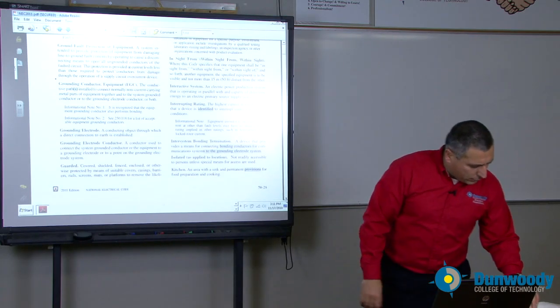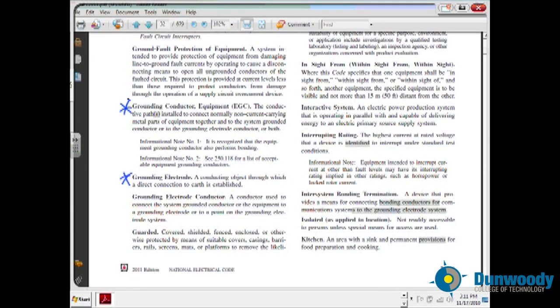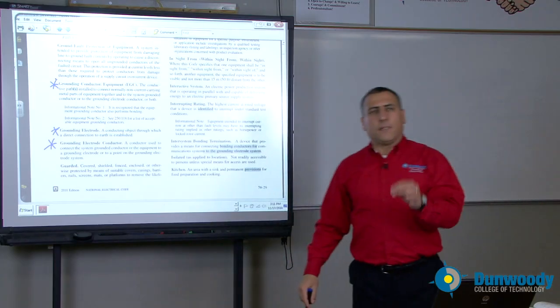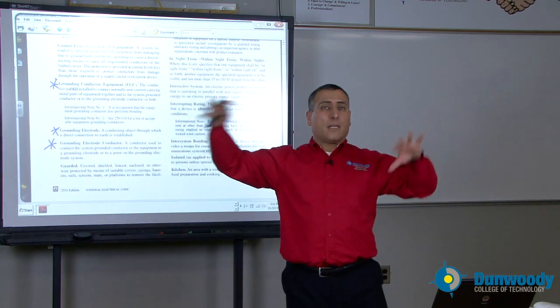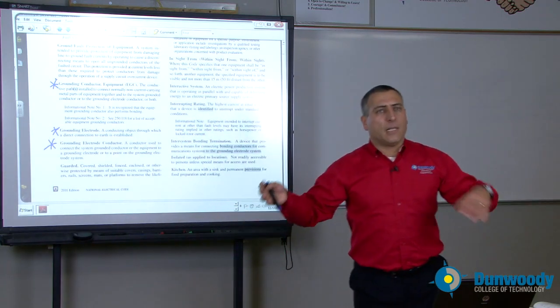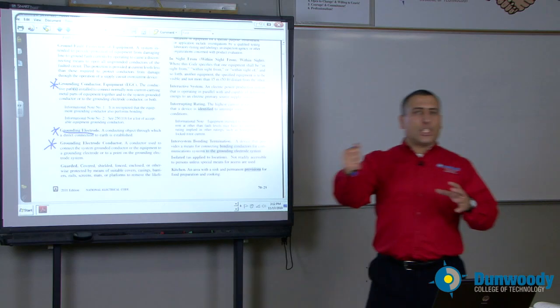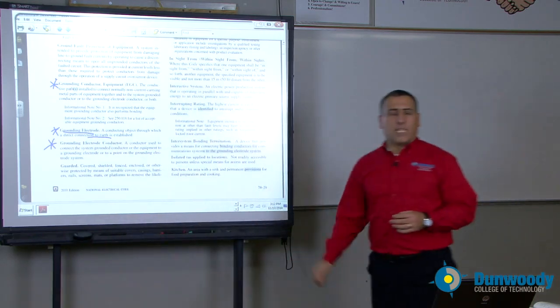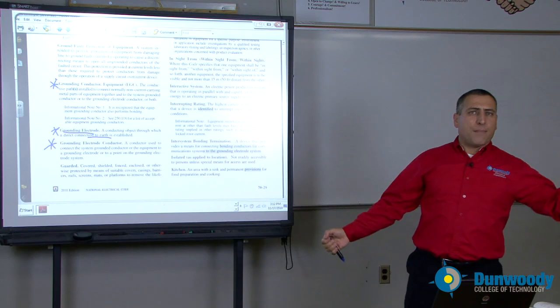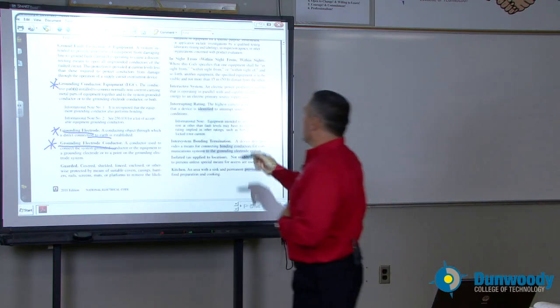Three topics: grounding conductor equipment, grounding electrode, and grounding electrode conductors — these are very unique, specific, different types of grounding systems. Equipment grounding conductor — that's the grounding conductor that grounds the equipment itself: a fan, a receptacle, a light. Grounding electrode — that's a conducting object through which a direct connection to Mother Earth is established, like a rod, a pipe, a ground rod, or a water pipe. Grounding electrode conductor — that's the conductor that ties your system directly into the ground.